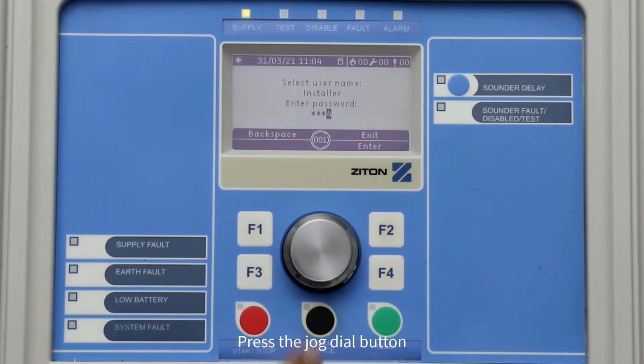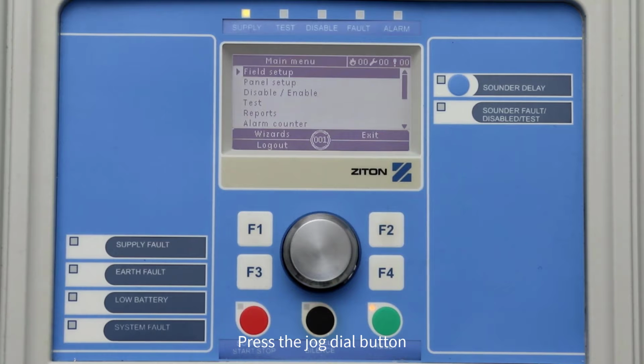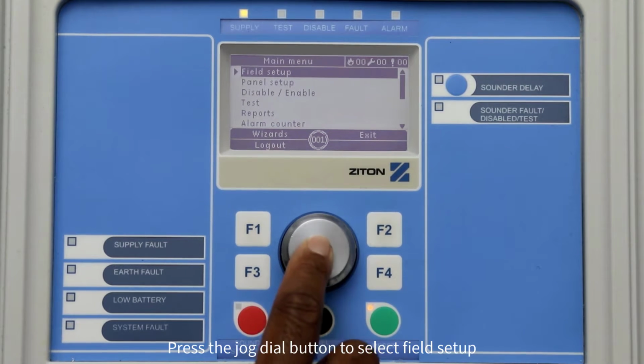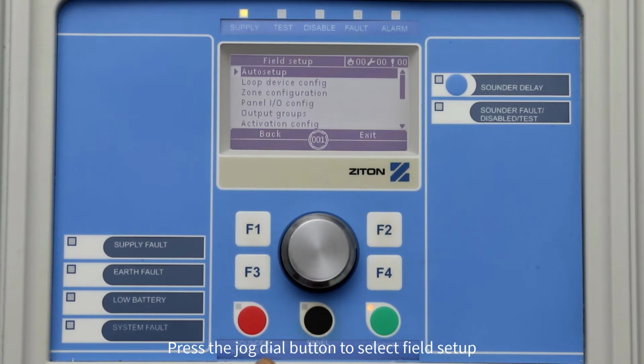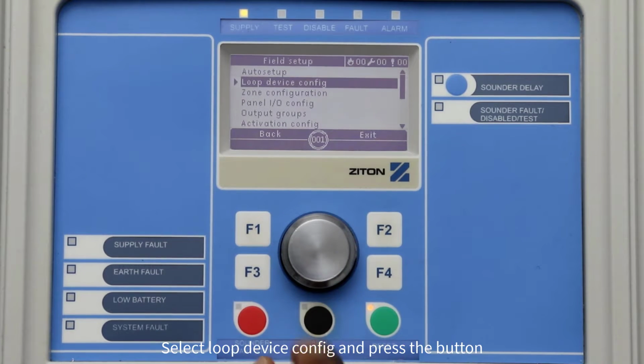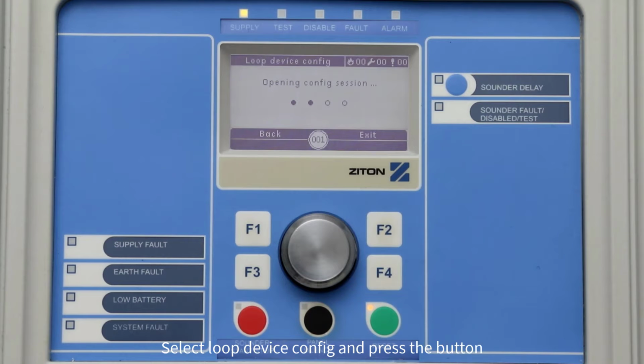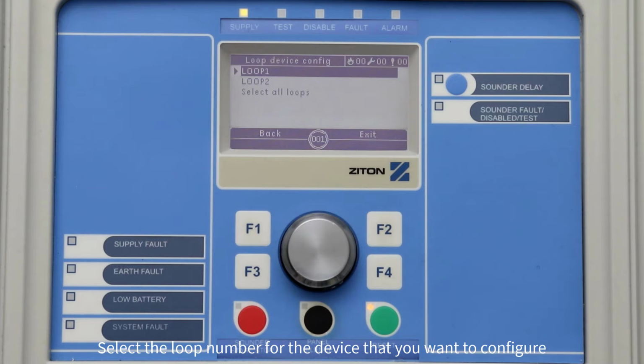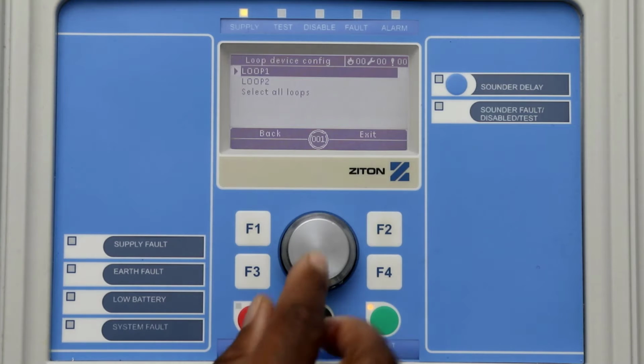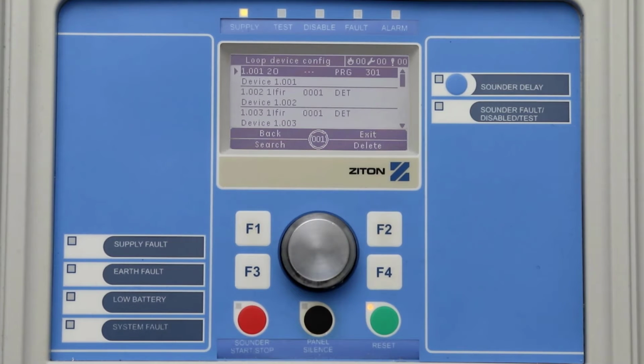Now press the jog dial button or F4 to enter into the installer menu. Press the jog dial button to select field setup. Turn the jog dial button and select loop device config, then press the jog dial button. Select the loop number of the device that you want to change its credentials. For this example, I will select a device on loop number 1.